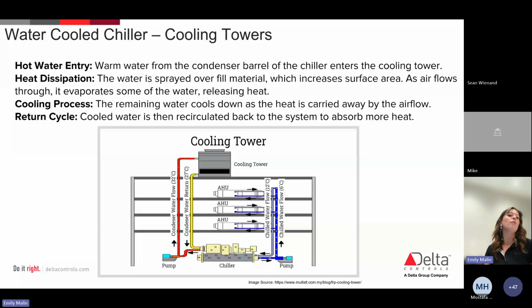We'll first go through an example of a chiller using a water-cooled system, so a cooling tower, and how this is actually working. So a cooling tower works with the water-cooled chiller to release all of that heat that is being absorbed through the building. So what's happening is warm water from the condenser barrel of the chiller itself is entering that cooling tower. Water is being sprayed over this fill material, which increases that surface area, and then air flows over it. And basically what's happening is it's evaporating some of the water, releasing that heat. The remaining water cools down as heat is being carried away by the airflow. And then that remaining water is recirculated back into the system to absorb more and more heat. So that's all that's really happening when you're looking at this cooling tower itself.